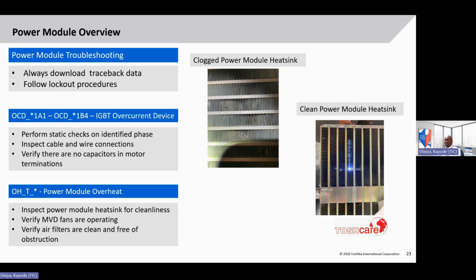And finally, this is probably going to be confirmed at startup, but if there's any doubt, you want to make sure that there are no capacitors in the motor terminations. There should only be cables in the motor termination box. That's just a quick overview on troubleshooting an OCD fault. Next, overheat, power module overheat. That's OHT. And as I mentioned, the asterisk refers to the phase that's affected.